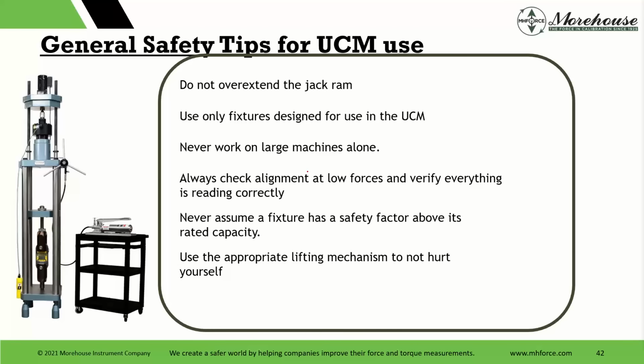So UCM, if you're using a UCM, I know some people on this call are, do not overextend the jack ram. What are we saying here? This piece is the jack ram. It's meant to have about an inch of travel. There is not any safety protocol in this to stop you from overextending the ram. We are working on that. We have built it for some. It's more expensive. Generally, we find that once people are trained, they do not want that additional safety. But if it's something that is a concern or you might have had frequent occurrence on, we do have options that can prevent that.